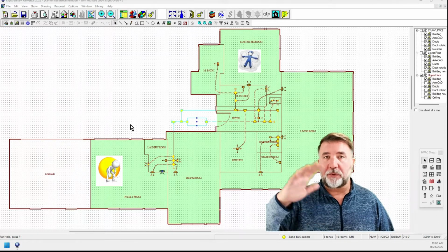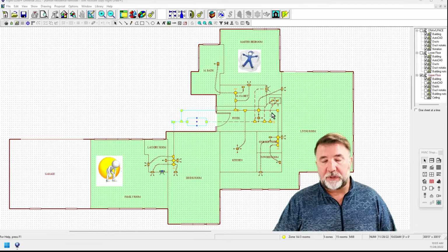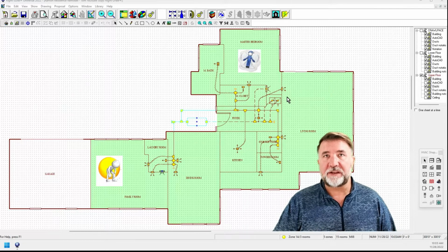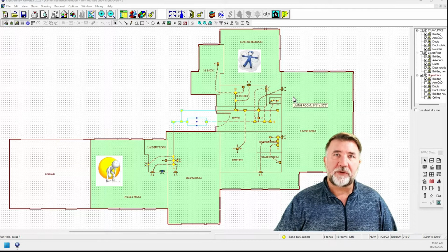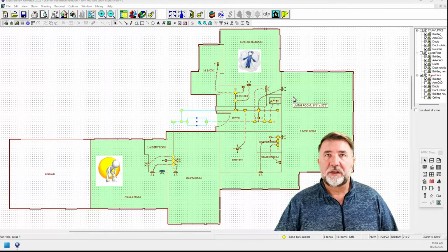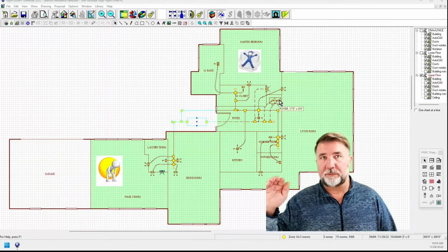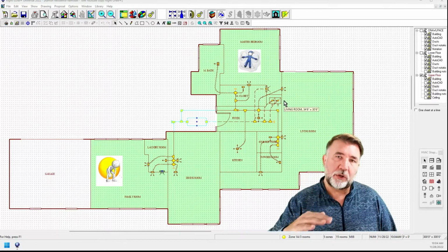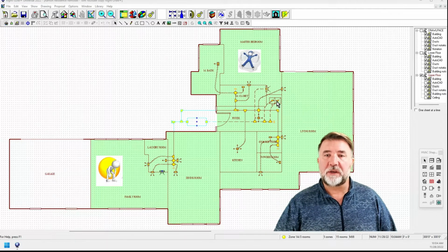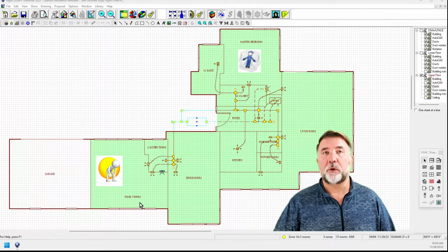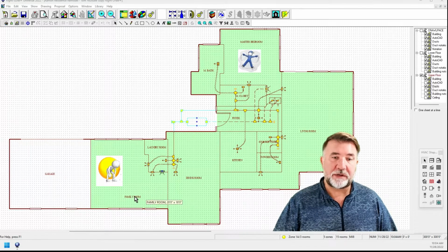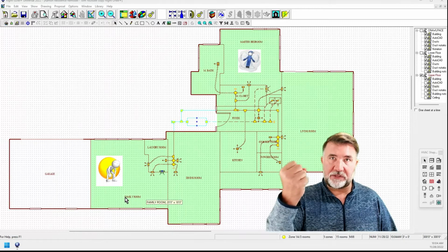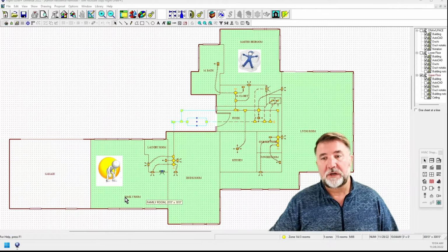Well, what will happen with the oversized system is, we're circulating this like 20 times, massive volumes of air. But what we need to be able to do is size it properly so that we're slowing the system down. And yeah, we may still get 20 over here, but because we've slowed the system down, we're giving it more time for us to get closer to 10 to 15 times of air circulation back over in these rooms, which allows it to remove the humidity and moisture much quicker.